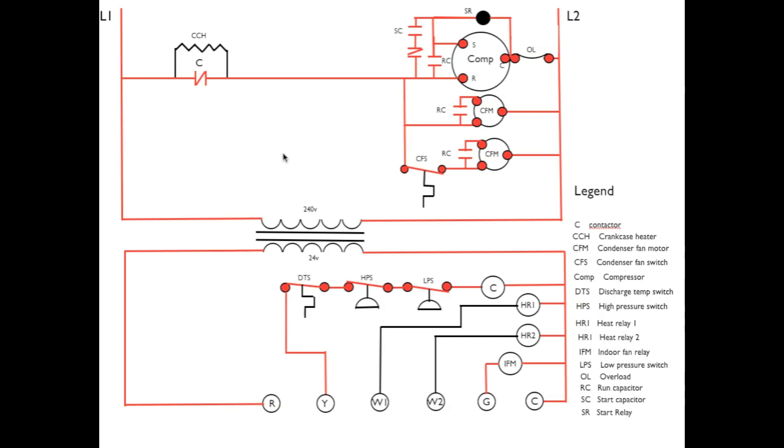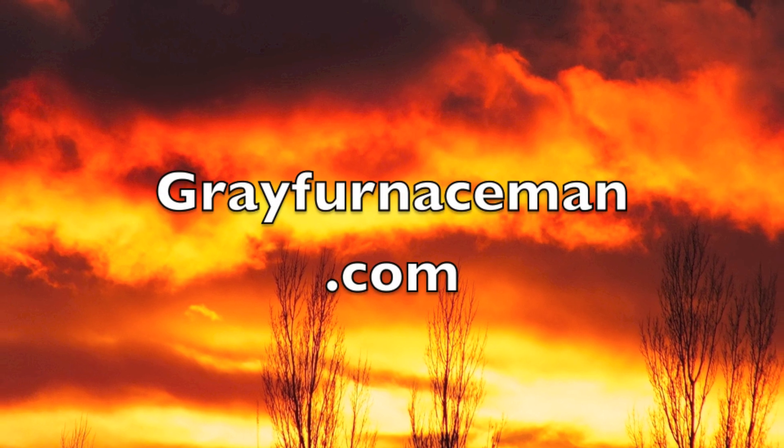Okay, the last part of this sequencing is we're going to close CFS. So, power will go through C, down through CFS, which is now closed, and it will energize the second condenser fan motor. And that's the cycling of this air conditioner. Thank you.